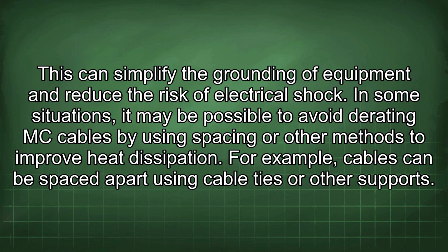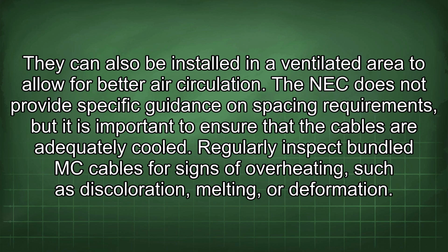In some situations, it may be possible to avoid derating MC cables by using spacing or other methods to improve heat dissipation. For example, cables can be spaced apart using cable ties or other supports. They can also be installed in a ventilated area to allow for better air circulation. The NEC does not provide specific guidance on spacing requirements, but it is important to ensure that the cables are adequately cooled.